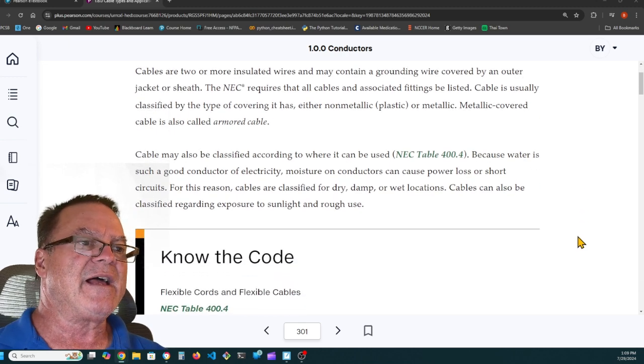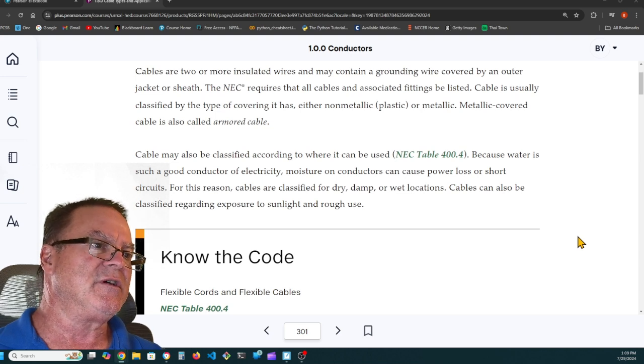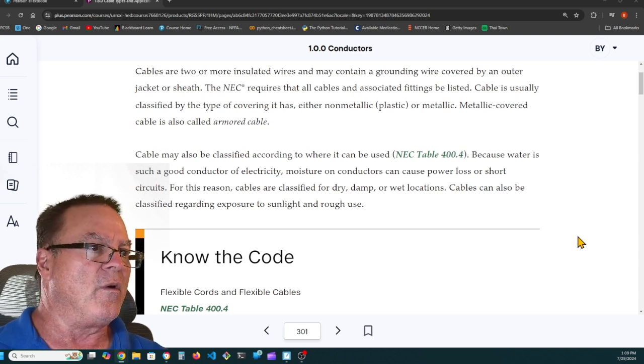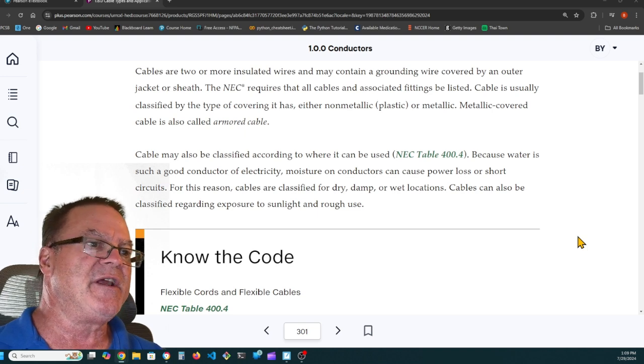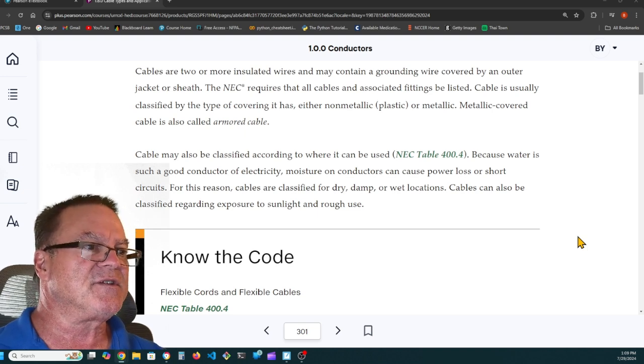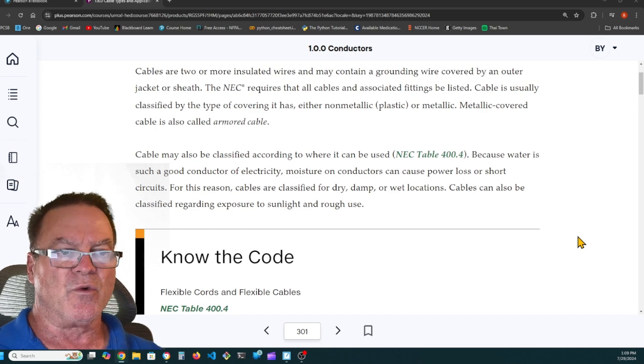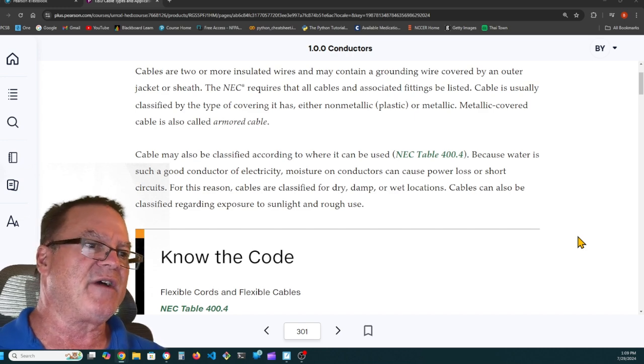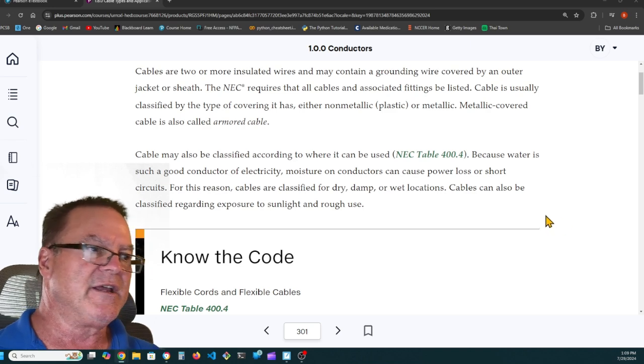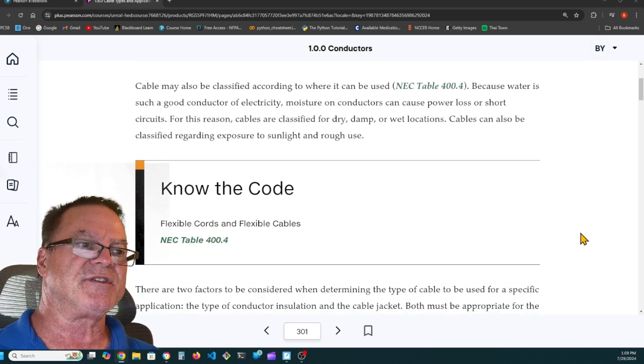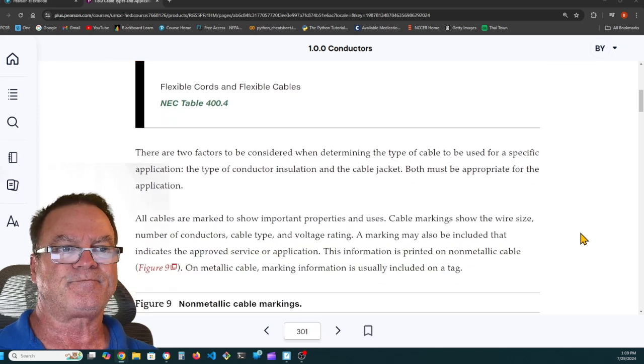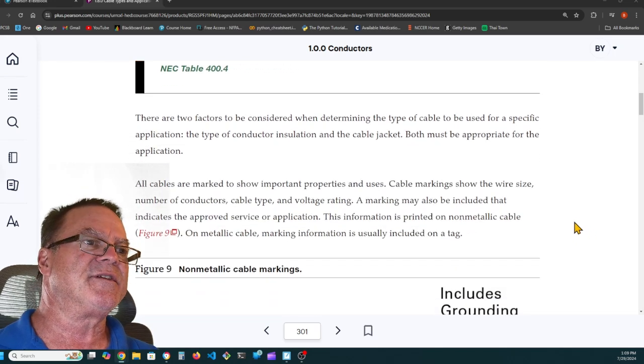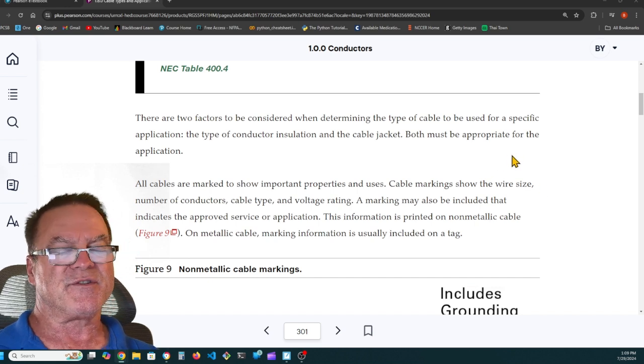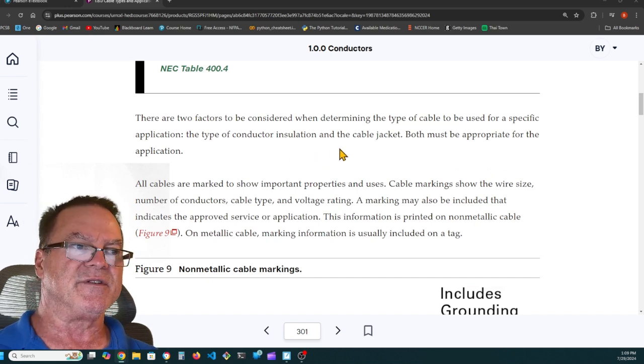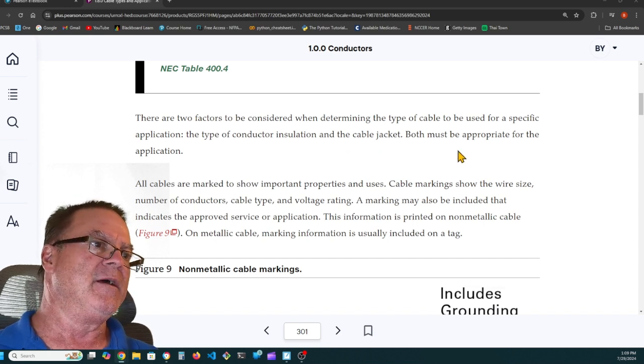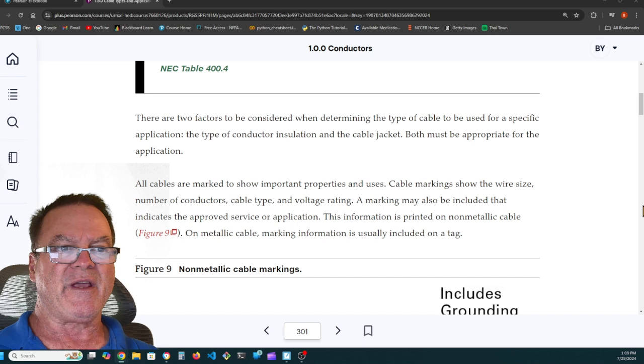Cable may also be classified according to where it can be used. NEC table 400.4. Because water is such a good conductor of electricity, moisture on conductors can cause power loss or short circuits. For this reason, cables are classified for dry, damp, or wet locations. Cables can also be classified regarding exposure to sunlight and rough use. There are two factors to be considered when determining the type of cable to be used for a specific application: type of conductor insulation and the cable jacket. Both must be appropriate for the application.